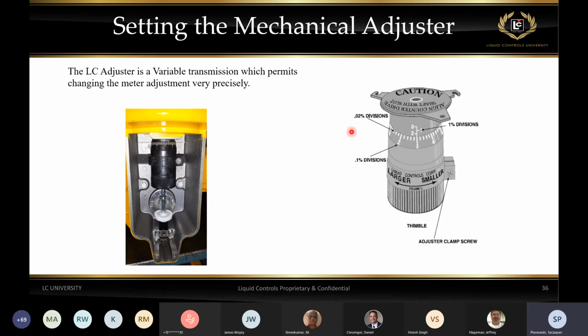The horizontal scale numbers represent 0.1%, and the hash marks between the numbers represent 0.02% of error. So it's a very, very precise device. We can adjust the reading of a counter by as small a number as 0.02%. Now again, that adjustment moves up and down on the scale. It can go close to 0 or close to number 5, which is at this point not visible. It's a little bit below. So how do we make that adjustment? How do we know which direction to go? How do we know by how much?